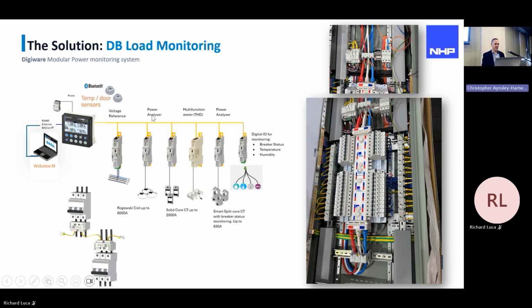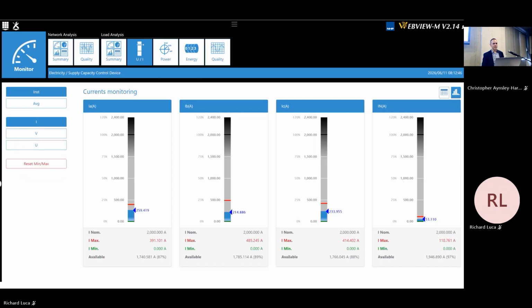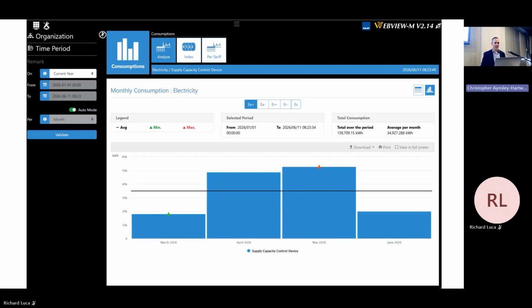So this system daisy chains back to a display or a gateway that gets fed back to the head-end system. And that's what it looks like when we interrogate the system. We see a snapshot. We can look at the currents on the individual phases, what the neutral's doing. So from a site-wide perspective, we've got visualization from the whole plant.